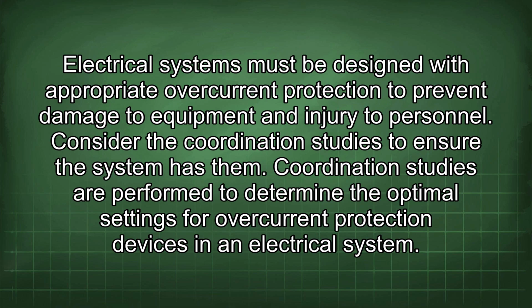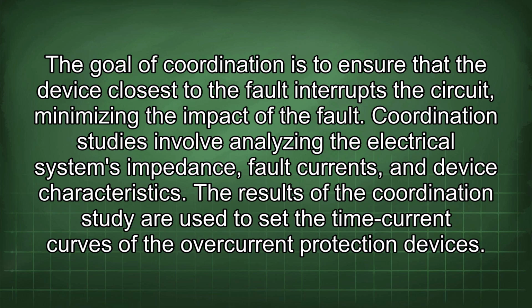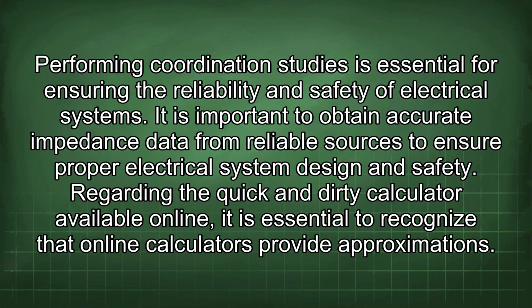Consider the coordination studies to ensure the system has them. Coordination studies are performed to determine the optimal settings for overcurrent protection devices in an electrical system. The goal of coordination is to ensure that the device closest to the fault interrupts the circuit, minimizing the impact of the fault. Coordination studies involve analyzing the electrical system's impedance, fault currents, and device characteristics. The results of the coordination study are used to set the time current curves of the overcurrent protection devices. Performing coordination studies is essential for ensuring the reliability and safety of electrical systems. It is important to obtain accurate impedance data from reliable sources to ensure proper electrical system design and safety.